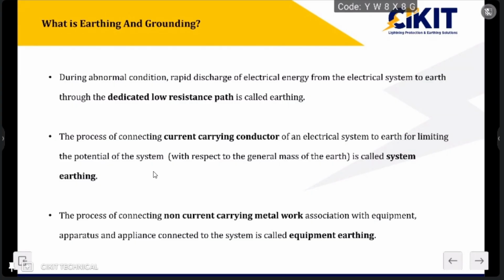One is system earthing, and another is equipment earthing. Everyone will be aware of the term equipment earthing. If I have any machine, I will connect the body of the machine to the ground for the safety of the operator. If I connect the non-current carrying metallic part of a system to the ground, it is called equipment earthing.